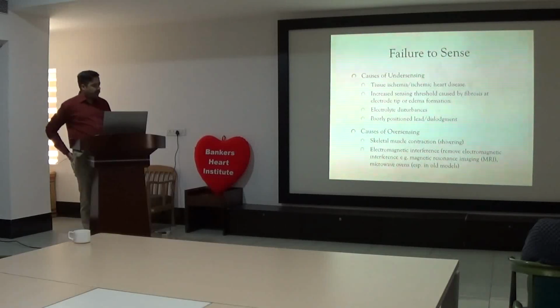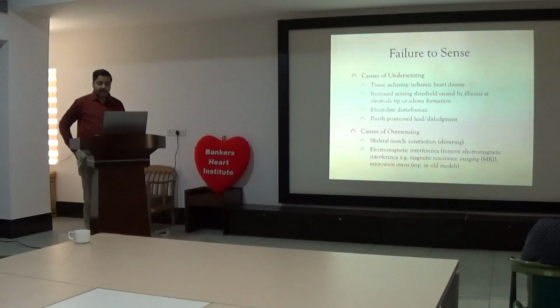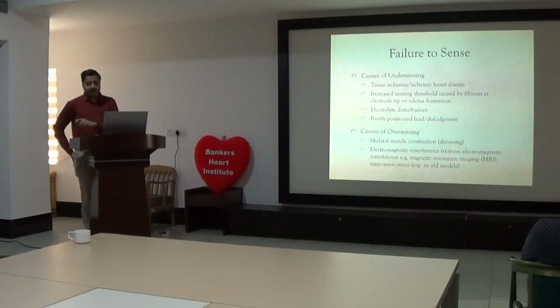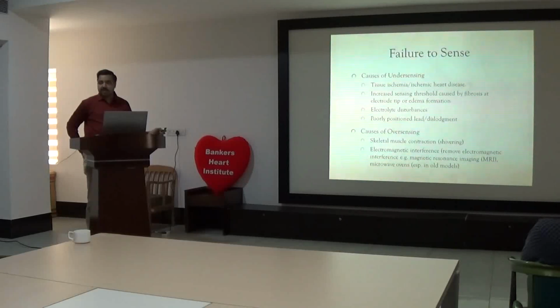Another cause is electrolyte imbalance because of hyperkalemia. The myocardium will go into a low responsive state and won't get an adequate amount of native depolarization, so the pacemaker is also going to undersense. And a poorly positioned lead: if your lead contact with the myocardium is not adequate, it will go into undersensing.